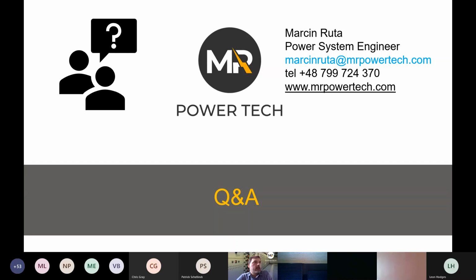Maybe I can elaborate a little bit on if you have a new switchgear that is internal arc classified, because that's very common. That's what I hear very, very often: if there is a new switchgear, we are on the safe side. Technically not. For calculation, it doesn't matter what kind of switchgear it is. Is it new or old? Of course, it makes a difference.